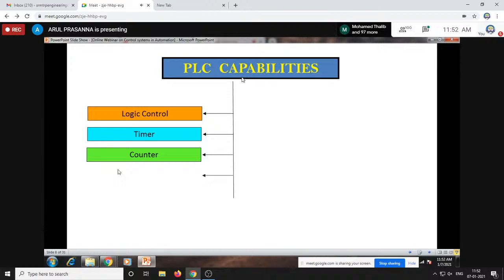Next is processing of analog signals. A PLC has the capability of processing analog signals if it is provided with an analog processing channel. PLC modules are available as digital only, digital with analog, or analog only. You can select whichever category suits your project. If your project has no analog inputs or outputs, you can go for a simple digital I/O PLC, meaning DI/DOs, which will be of very low cost.